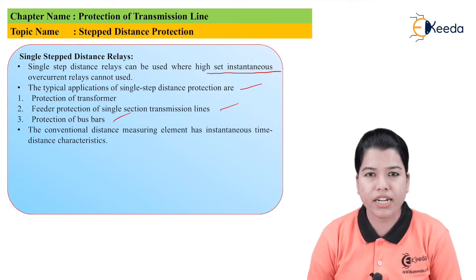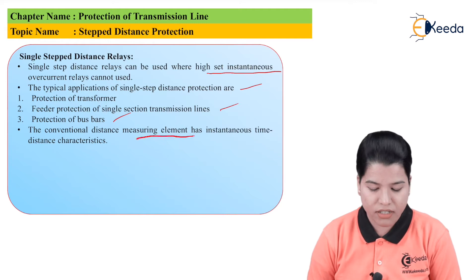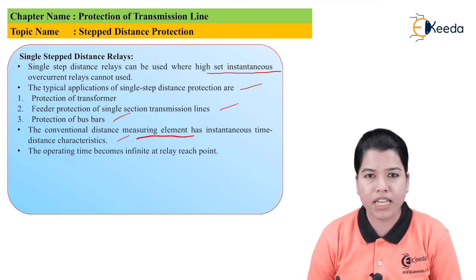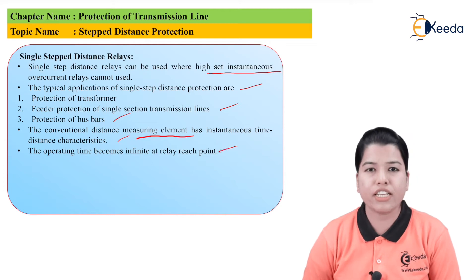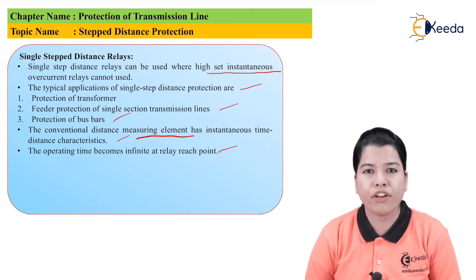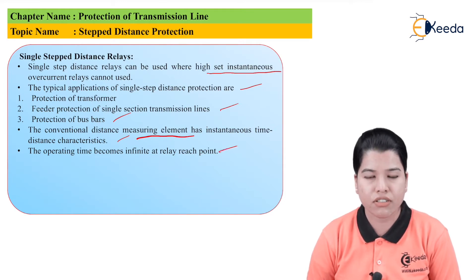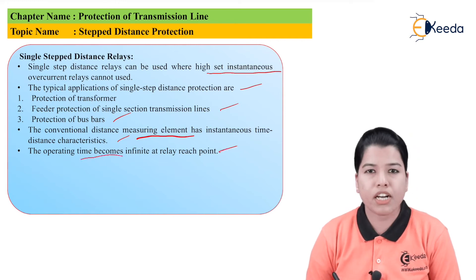The conventional distance measuring element has an instantaneous distance characteristic, meaning it operates instantaneously. The operating time becomes infinite when the relay reach point is reached. The reach is defined as the distance up to which the protective relay will operate, or the distance up to which the distance protection can be applied. Whenever this reach is exceeded, the operating time becomes infinite.